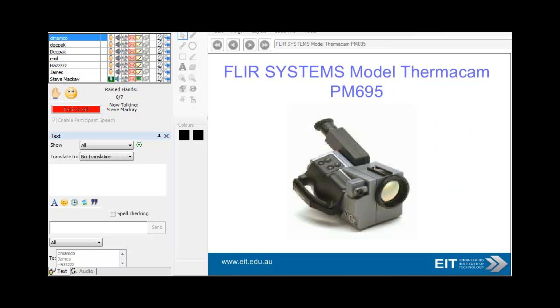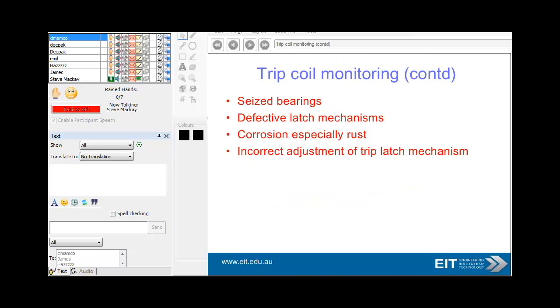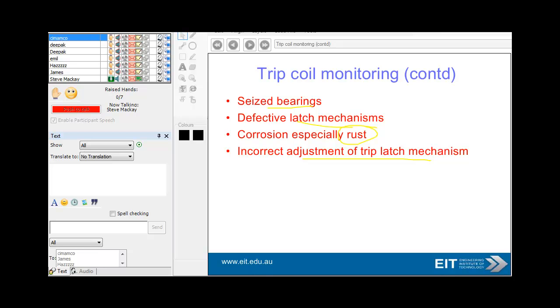Here's a thermal grayscale image of an air-break disconnector. Trip coil monitoring is quite important — statistically, trip mechanisms and trip coils are responsible for most failures to operate, and you obviously want to operate 100% of the time. Failures can often be due to improper lubrication, shorted turns in the trip coil because the winding insulation has deteriorated over time, faults in secondary wiring and secondary wiring contacts, seized bearings, defective latch mechanisms, rust and corrosion, and incorrect adjustment of the trip latch mechanism.